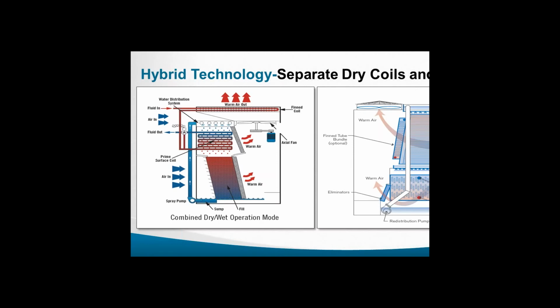And the water saving capability of these units is maybe not as great, and the dry switchover point not that high. Yeah, both of the systems. So what's the typical temperature then if you would switch over from dry to wet? It depends on your application.